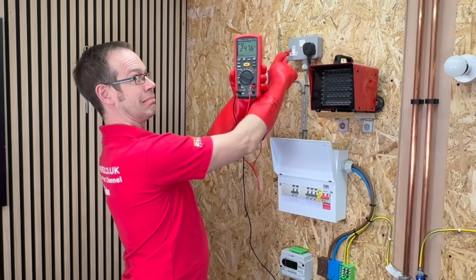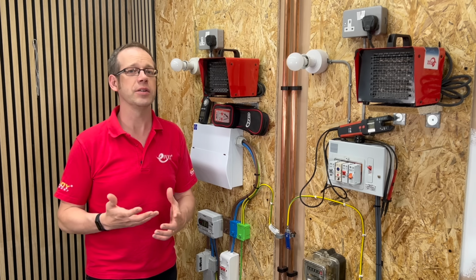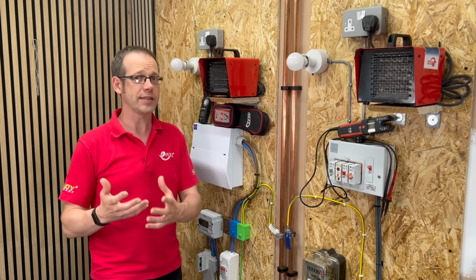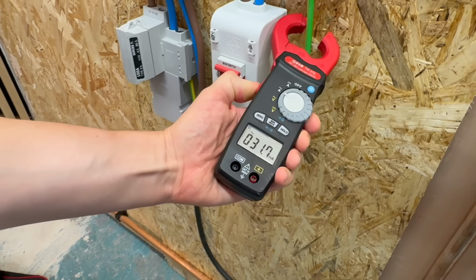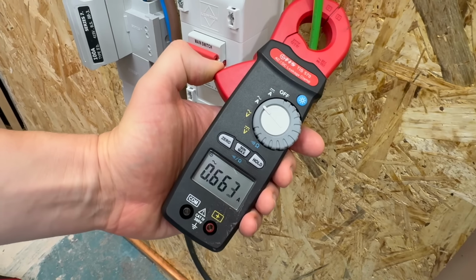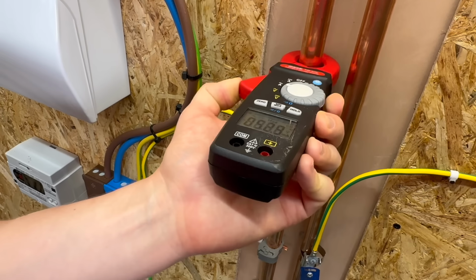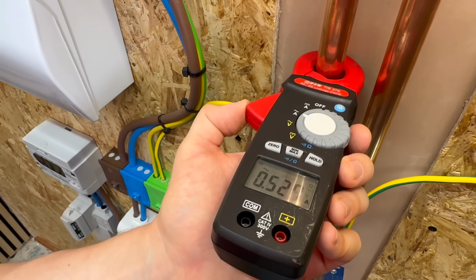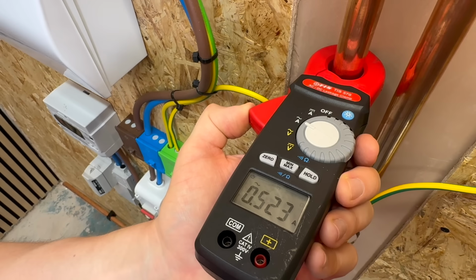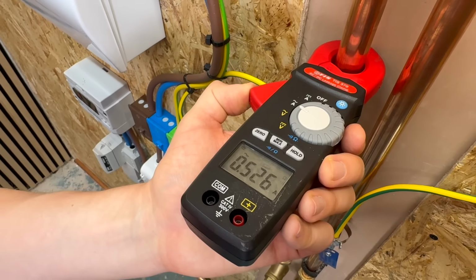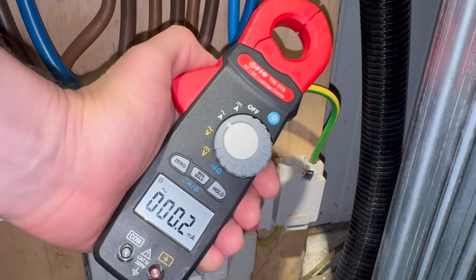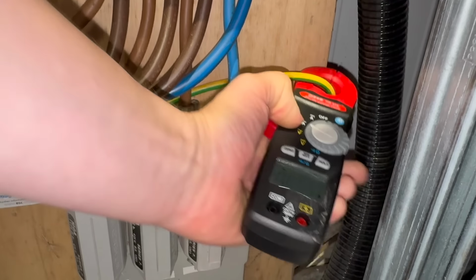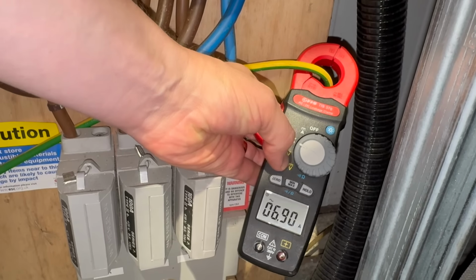One way that I could detect this problem and potentially protect myself from the danger is, before disconnecting anything, just to pop a clamp meter around the main earthing conductor, the bonding conductor, or even the metallic water pipe. If there's a significant current reading, then it could be a sign that there is a problem. Unfortunately, like so many things in the electrical industry, it's not always that simple, because you might read a current flowing in these conductors even when everything is completely healthy. Let me explain how.